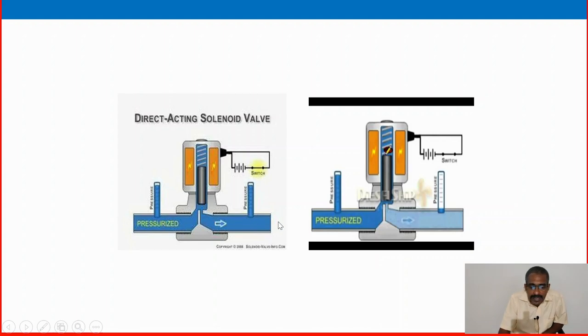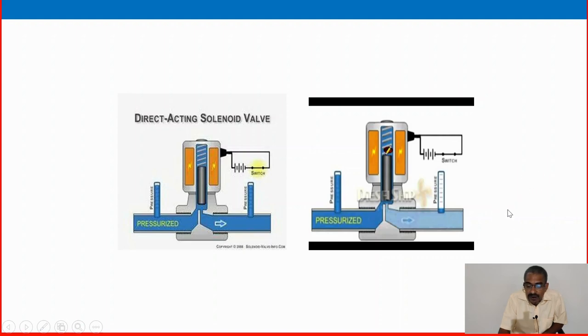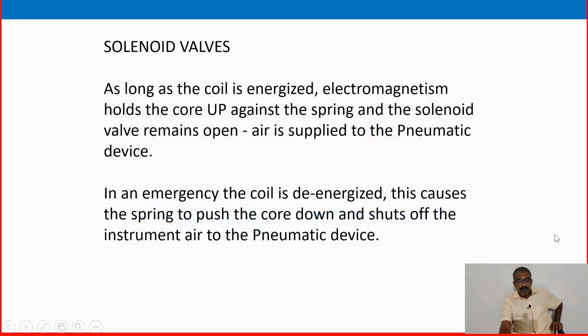Then the pneumatic air passes through the solenoid valve, and that compressive pneumatic air supplies to the ESD valve — to the driver, to the pressure drum and piston. Once the ESD event happens, the logic is activated. The electrical switch is disconnected and de-energized. Immediately the magnet is de-energized and the solenoid valve becomes closed. So pneumatic air cannot go in. Pneumatic air not going means the downstream ESD valve will go to its normal position — whether fail to open or fail to close — that valve will go to its normal position.